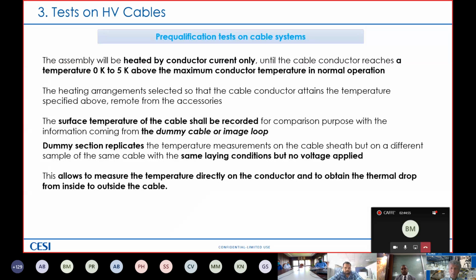The surface of the cable should be recorded for comparison purposes with the information coming from the dummy cable, or so-called image loop. Of course, the dummy section replicates the temperature measurement on the cable sheath, but on a different sample of the same cable with the same laying condition, but no voltage is applied. Of course, this is the big difference. In a dummy cable, we can drill up to the conductor and install the thermocouple on the conductor because we do not apply the voltage.